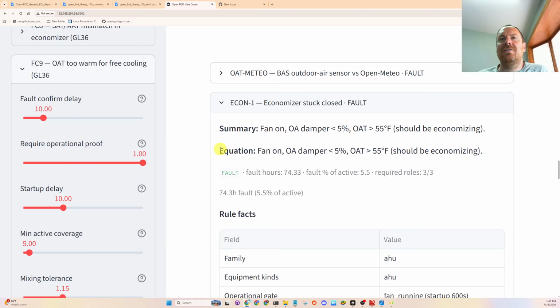Okay, so I would gloss this over again. The way that these rules are written, there's not enough tunables on the side. I like to go off of this outdoor air dew point concept, below 60 with the dry bulb below 72 degrees Fahrenheit, as a web weather station way of saying we could be economizing off of outdoor dew point. So I'll be refining some of this.